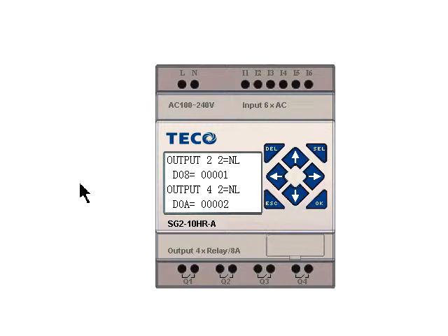For more advanced users, this will be set by the factory in all cases, but you can reassign outputs 2 and 4 to the no load alarm. So the no load alarm can run through the control. So if you have a single material loader, you can set output 2. So instead of being material 2 that is set up as standard, it would activate when the no load alarm took place. And you can do the same thing with output number 4. You can set that so that it will activate when the no load takes place instead of the blending option, which is standard. And that's it.